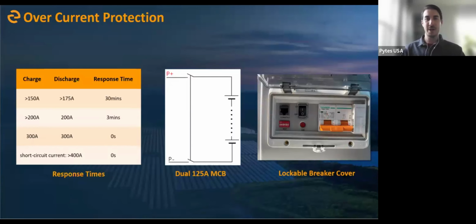So when you look at a contactor BMS, the response times can be a little slower. And that means that if you have an overcurrent event, maybe the breaker on the battery would trip. And now when that overcurrent event goes away and things go back to normal, the breaker's still tripped and you have to do a manual reset. Whereas if we let the BMS manage that instead, like a MOSFET BMS would, it's just going to turn off and then turn back on as soon as that fault current goes back down to a normal level or goes away.